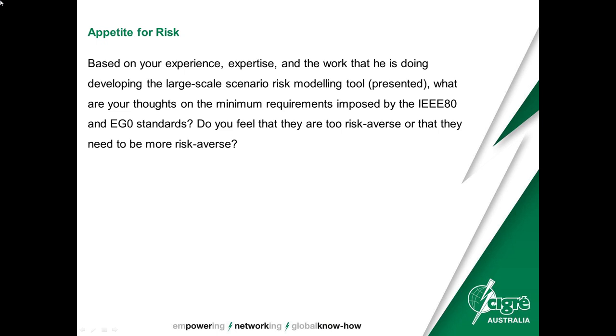So in some cases, there'd be tens or even hundreds of thousands of dollars spent to bring touch voltages down in locations just to meet a voltage criteria. The gut feel of myself and other engineers was that seemed wrong. It seemed like a bad investment. But because it was a black-and-white voltage criteria, you either spent the money and lowered the voltage, or you turned a blind eye to it.